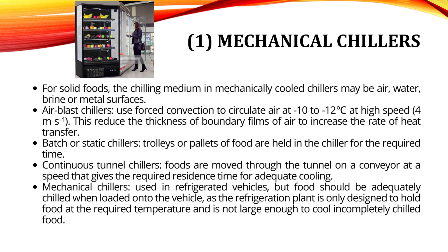In batch or static chillers, trolleys or pallets of food are held in the chiller for the required time. In continuous tunnel chillers, foods are moved through the tunnel on a conveyor at a speed that gives the required residence time for adequate cooling. Mechanical chillers used in refrigerated vehicles maintain food temperature, but food should be adequately chilled before loading, as the refrigeration plant is only designed to hold food at the required temperature, not to cool it.